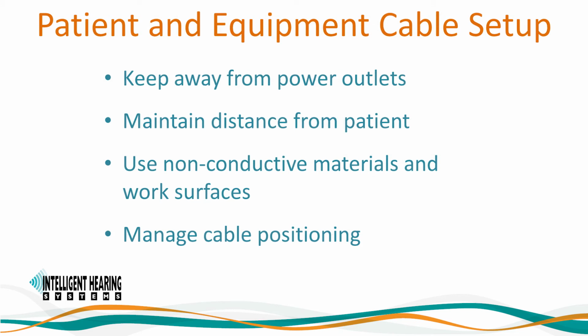Keep distance from power outlets. Do not position equipment near sockets or power line mains. If a bed is used, move it away from any wall with mains sockets. Next, maintain distance from the patient. Position equipment at the end of the bed on the patient's head side, but as far away from the patient as possible.